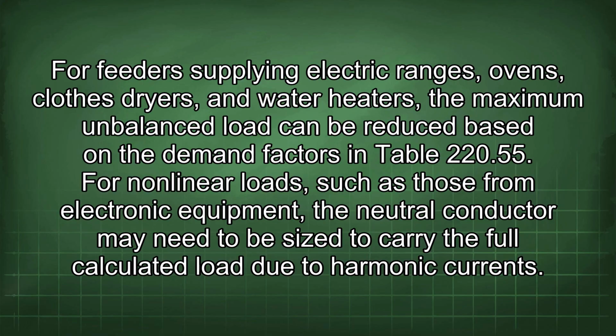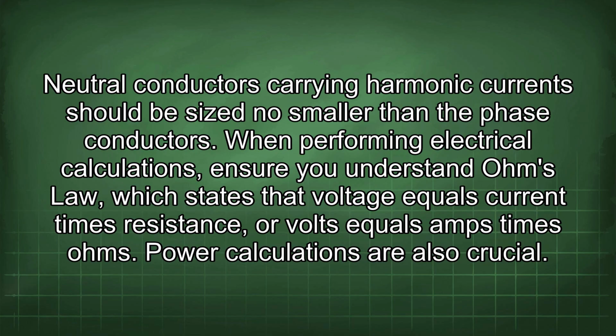For nonlinear loads, such as those from electronic equipment, the neutral conductor may need to be sized to carry the full calculated load due to harmonic currents. Neutral conductors carrying harmonic current should be sized no smaller than the phase conductors. When performing electrical calculations, ensure you understand Ohm's law, which states that voltage equals current times resistance, or volts equals amps times ohms. Power calculations are also crucial.